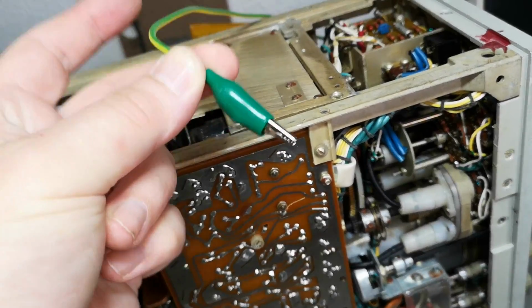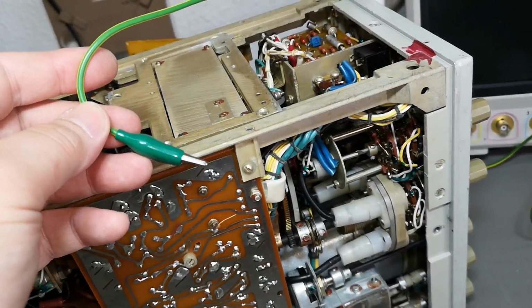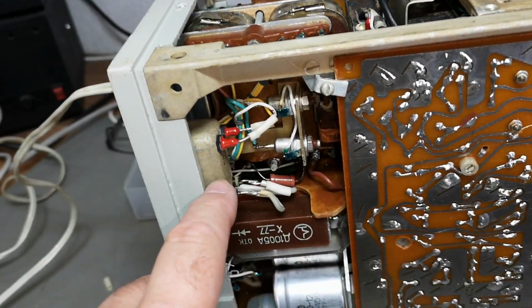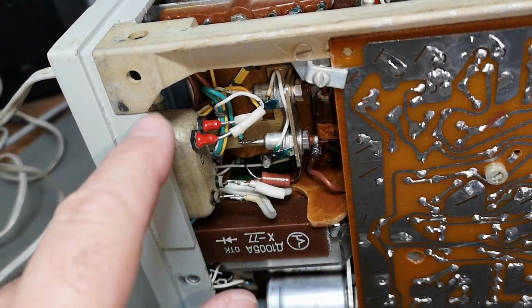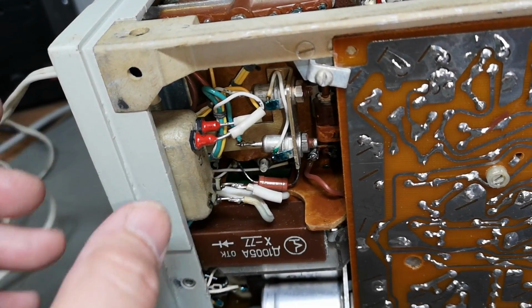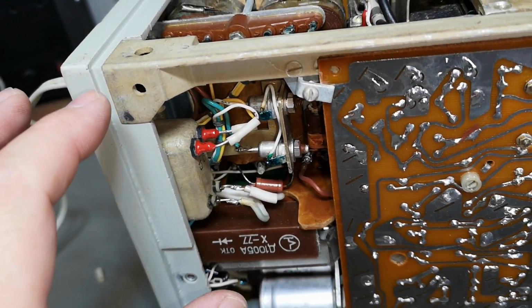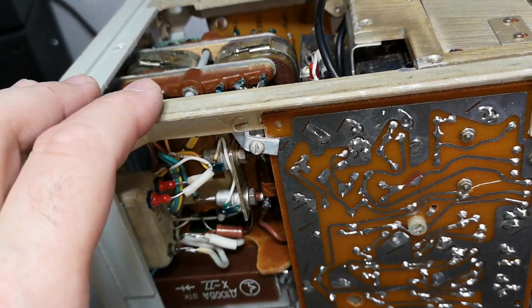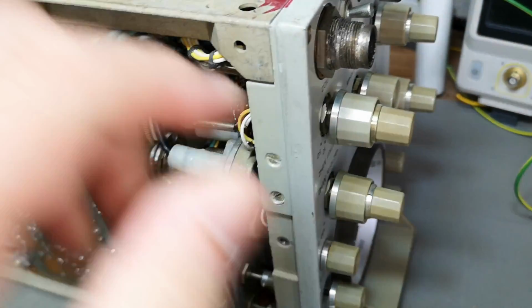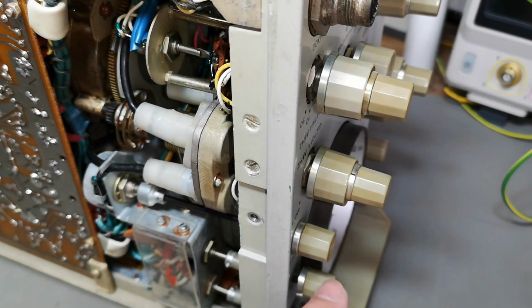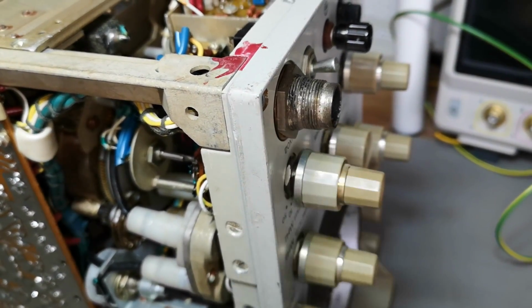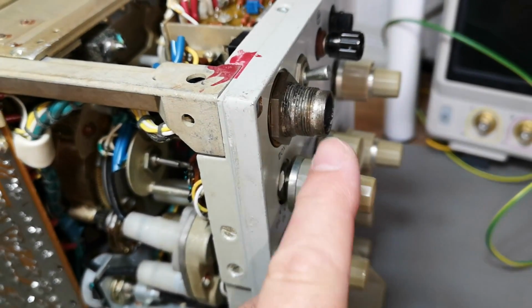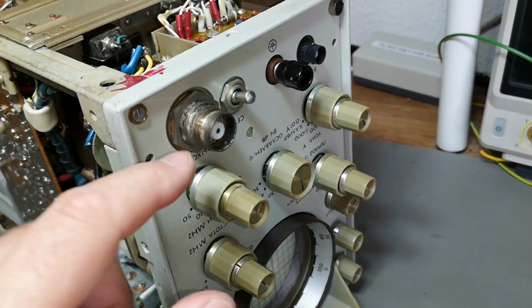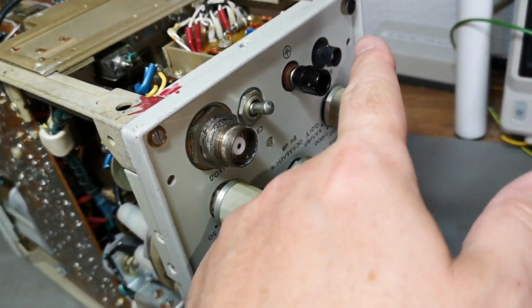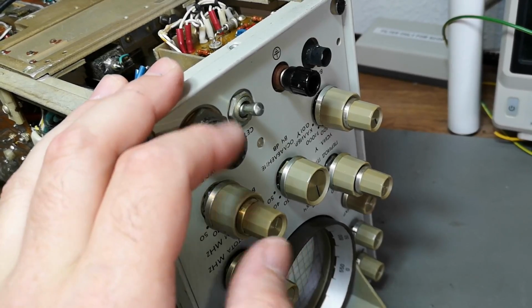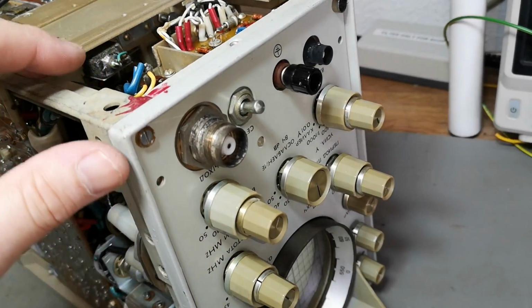Always do this, guys. This will save your life, because what happened in this case is that there is something wrong with the mains entry filter, and there is a leak to chassis here in that filter. So if you don't have this ground, the unit's probably gonna run, and there's something on the display, and when you poke around with all the different plastic knobs, you don't even realize this. First time you touch some metal here, you're going to get an electric shock, or even worse, I don't know if that is even worse, but you could potentially connect this to some of your much more nice and new and expensive equipment and blow something up.